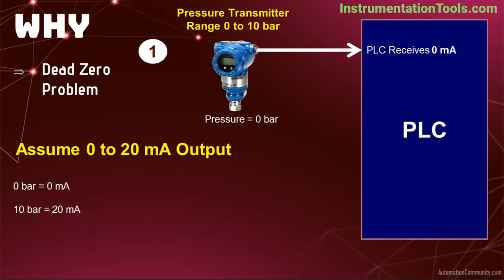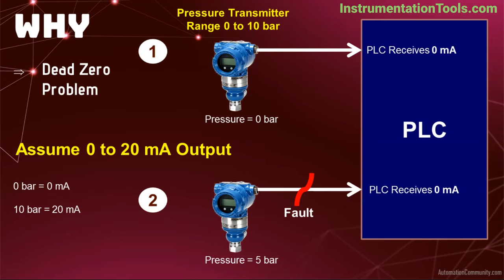Case 1: Assume the process pressure is 0 bar, so the pressure transmitter sends a 0 mA signal to the PLC, and the PLC displays 0 bar pressure to the operator. Case 2: Consider a fault in the pressure transmitter loop. The fault may be a broken wire, faulty transmitter, noise, high wire resistance, or any other problems. Assume the wire is broken between PLC and transmitter, and the process pressure is 5 bar. Because of the broken wire, the PLC receives 0 mA instead of 10 mA. The PLC thinks it receives 0 mA and displays 0 bar, but in reality it should be 5 bar. This is the dead zero problem.